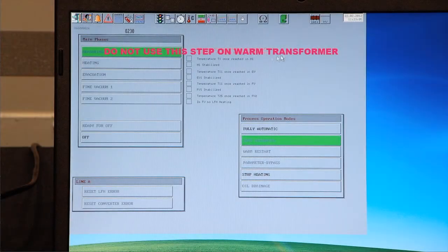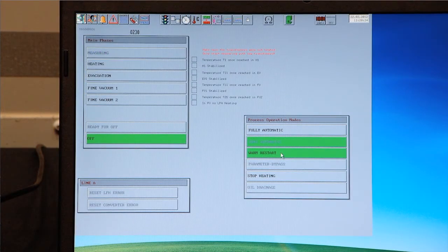Measurement step. This step should not be carried out if the transformer has been previously heated up. If this step is carried out on a transformer that is still warm from heating, then the temperature setting will not be correct, and that could lead to overheating that could destroy the transformer.